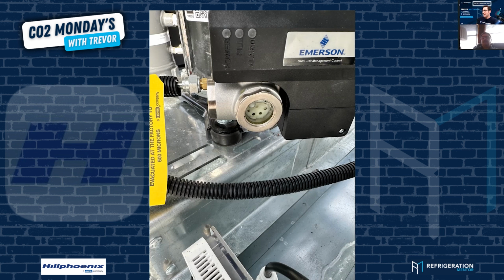That's a good one. We've had some commissioning companies come in and tell the contractors, hey, this is a plus 25 degree rack, you need to raise the suction pressure to 440. They do that, and within a week to 3 weeks they're tripping on oil. 440. That's high. I haven't heard of somebody running them that high. No, we run 400. You run 400. I've heard of some people at 420, and 410, but I never heard 440. That just means you would have to raise up the receiver pressure, and then that's risking the temperature of your product now, right?